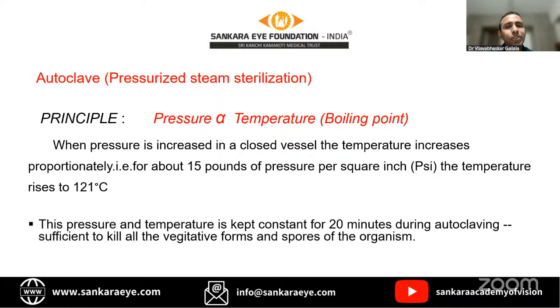At atmospheric pressure, the boiling point is 100 degrees. If you raise the pressure up to 15 pounds per square inch, the boiling point will reach 121 degrees centigrade. So to create the moist heat, you need to increase the temperature up to 121 degrees centigrade. If you expose these instruments to 121 degrees centigrade for 20 minutes, that is sufficient to kill all vegetative forms. That's how this autoclave works.